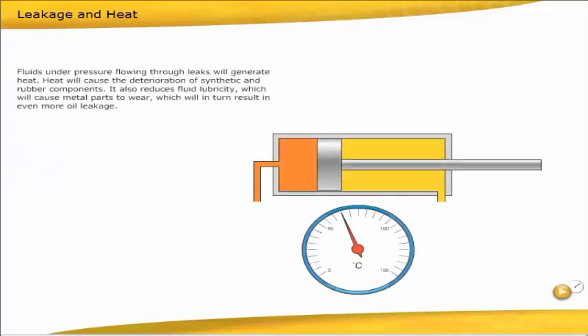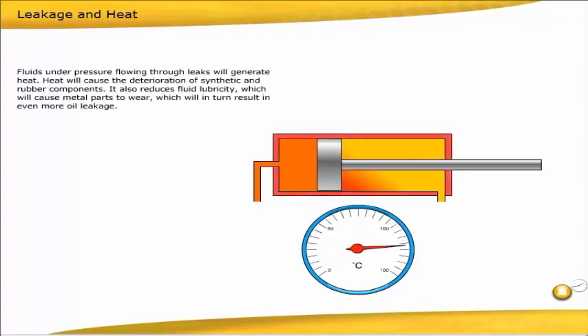Fluids under pressure flowing through leaks will generate heat. Heat will cause the deterioration of synthetic and rubber components. It also reduces fluid lubricity, which will cause metal parts to wear, which will in turn result in even more oil leakage.